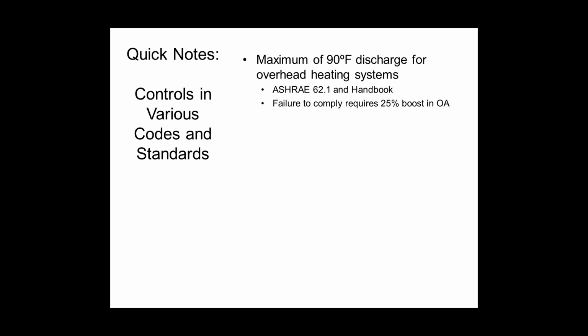So don't let the air discharge get really warm coming overhead. Keep it below 90 degrees. I've told some of you before, I used to go to jobs as a controls contractor, especially on rooftop jobs, and I used to literally take my snips out and cut the second stage of heating wiring because the people in the space were saying they were too cold. So I would disable second stage heat. Because if it's too hot, it hugs the ceiling and goes right back out the return. The thermostat always gets exactly what it wants. It's always going to be 73 degrees or whatever you set it for.